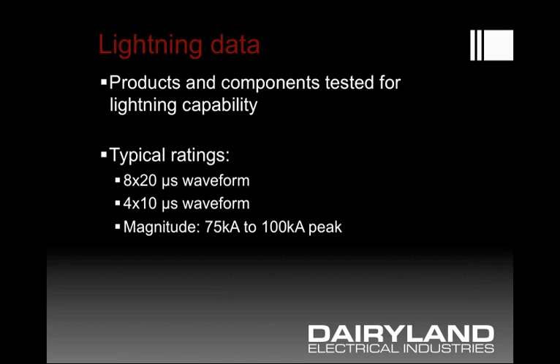Products and components are tested for their lightning capability. Typical values use an 8 by 20 microsecond waveform, or 4 by 10, to a reasonably high peak value of 75 to 100 kA.